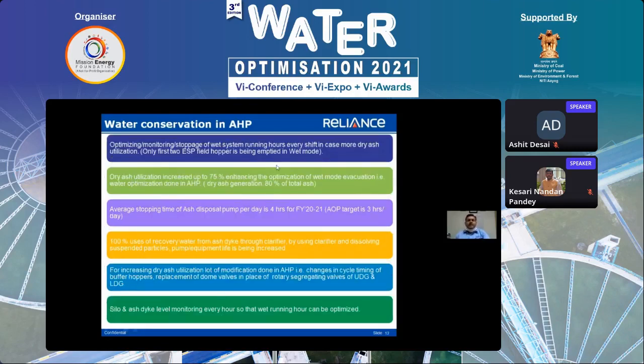Like we are monitoring the hopper evacuation. Only the first field hopper we sometimes take in the wet mode. The rest of the hoppers we empty by dry mode only, because we have done numerous modifications. We have around 4,000 to 4,500 metric ton of dry ash being disposed every day.